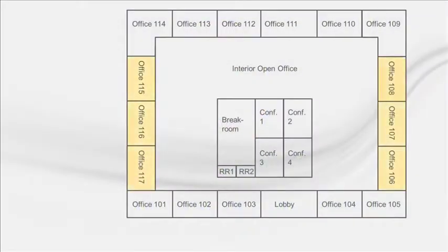The ultimate goal of zoning a heat recovery system would be to equalize the cooling and heating loads on the same heat recovery system. Coupling the east and west offices from the previous example on one heat recovery system will likely result in some savings in simultaneous heating and cooling. However, this requires longer and more extensive refrigerant piping, and as Dave mentioned, can be challenging in terms of compliance with ASHRAE Standard 15.